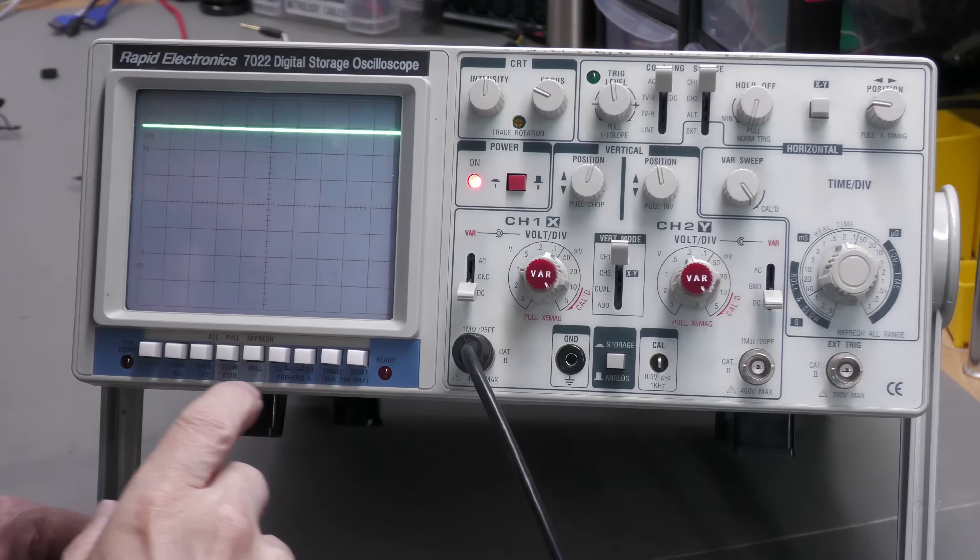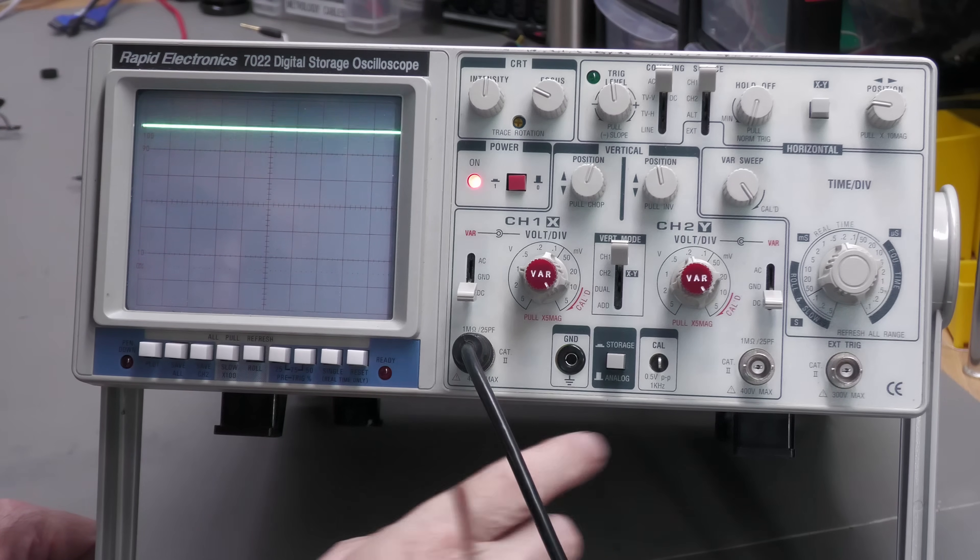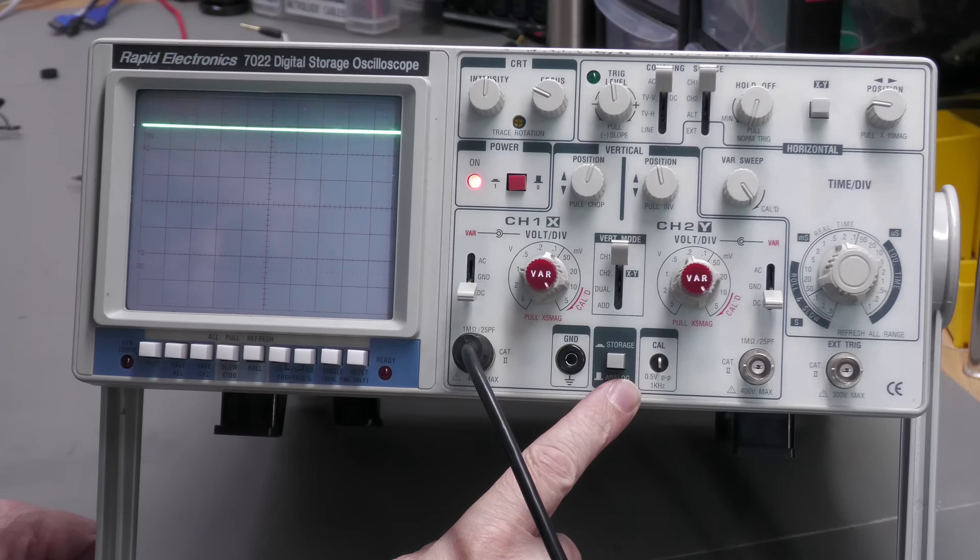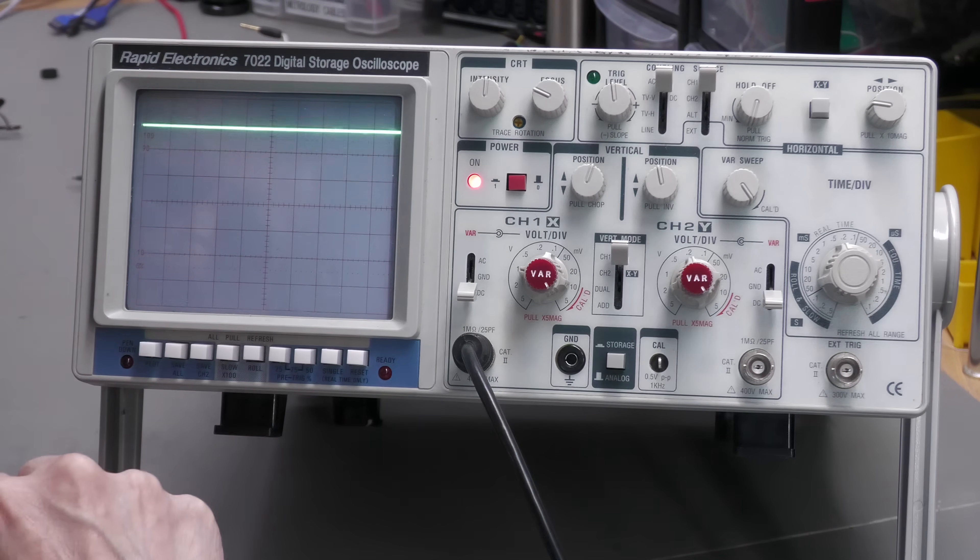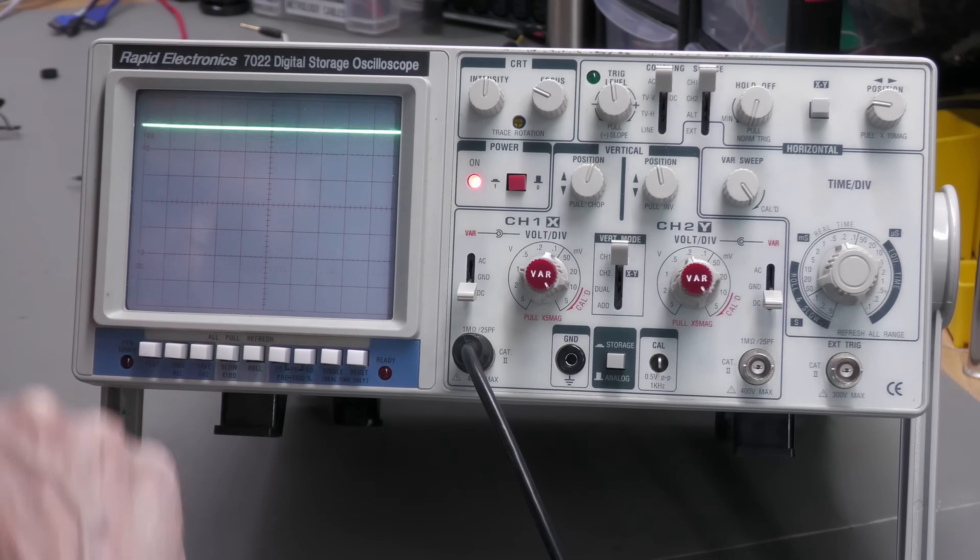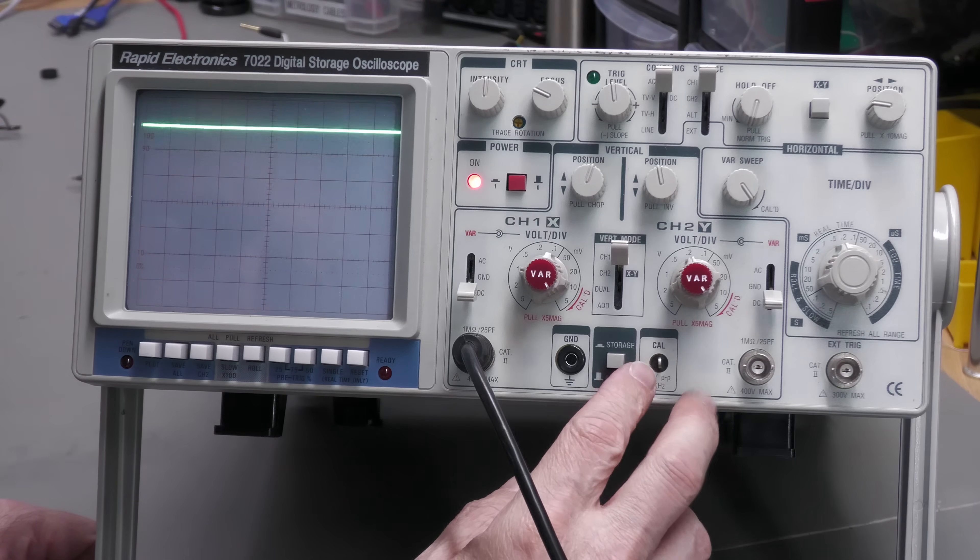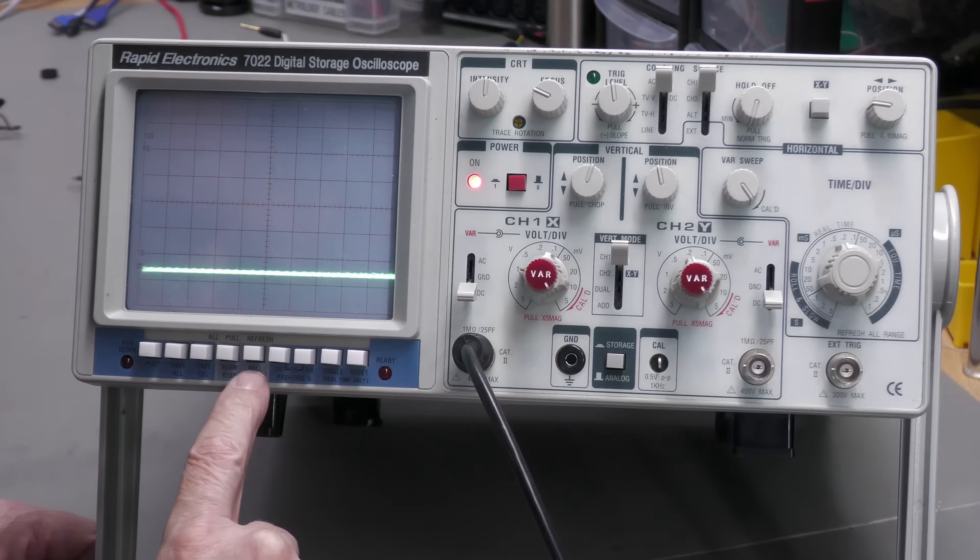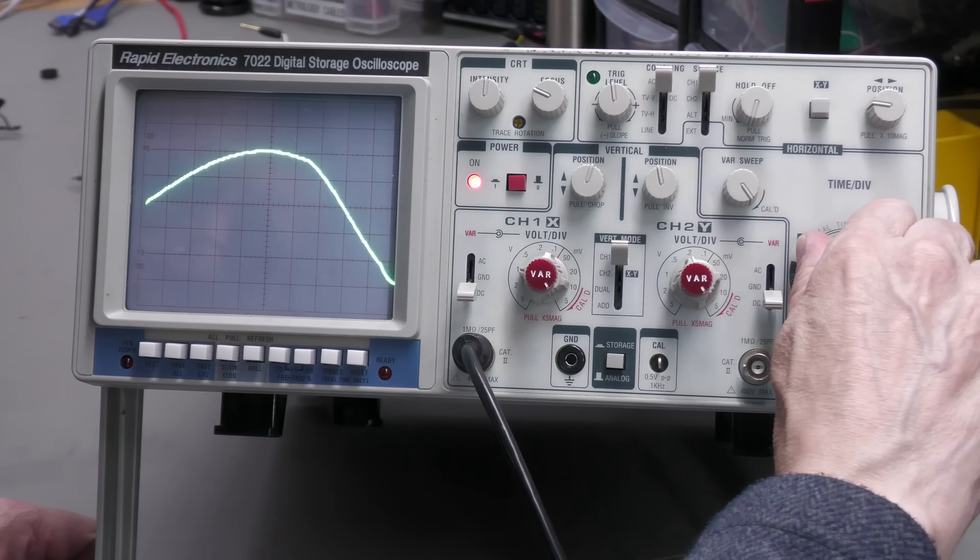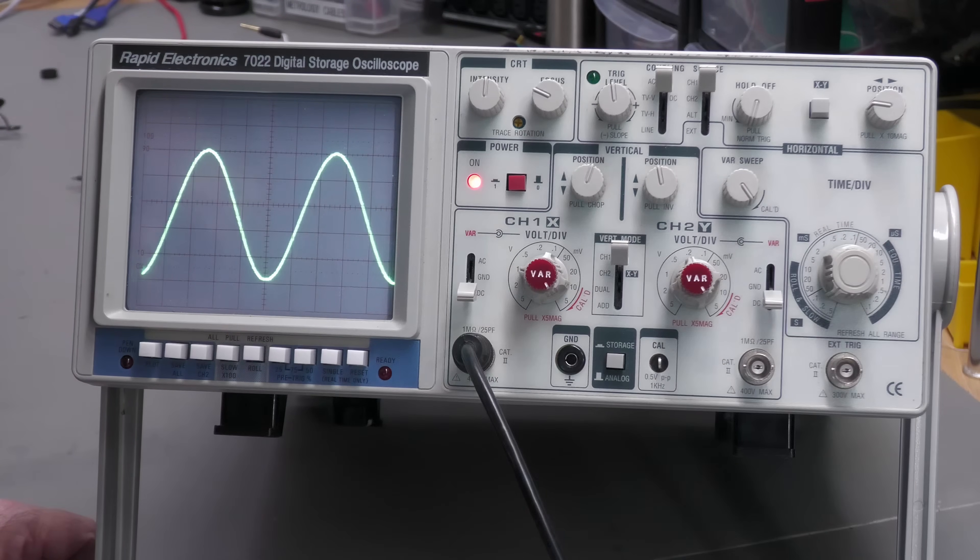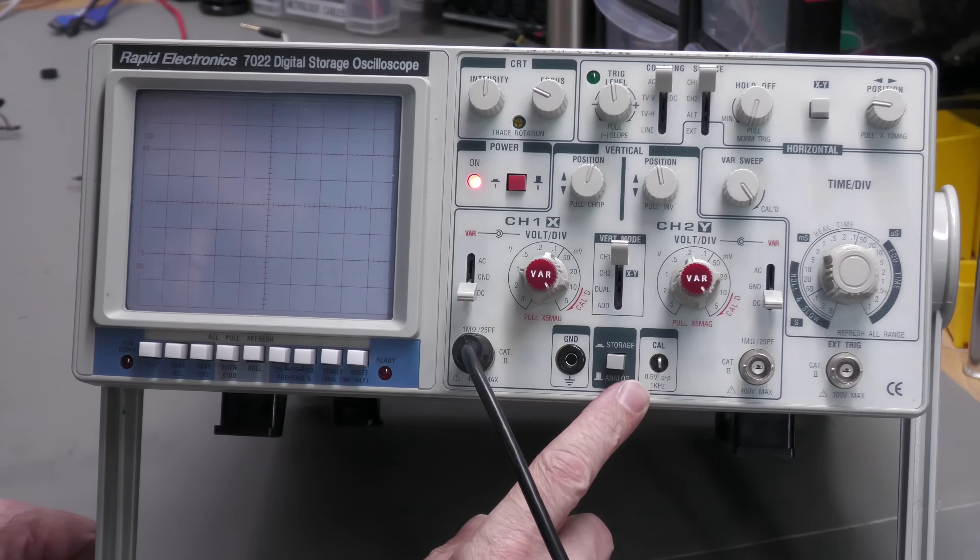A small demonstration of roll mode. I'm back on the analog mode at the moment. And I've got a one hertz sine wave coming in. And obviously you can see that there. If I now enable digital mode with the roll mode enabled and I've moved the time base back, then that's what you get.